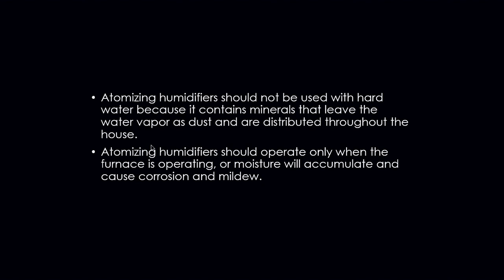Okay, atomizing humidifiers should not be used with hard water because it contains minerals that leave the water vapor as dust distributed throughout the house. Atomizing humidifiers should operate only when the furnace is operating, or moisture will accumulate and cause corrosion and mildew. So I'm going to say that again. Humidifiers should only operate when the furnace is operating, which means when our thermostat calls for heat, we are also going to send the signal to the humidifier as well. We do not want humidifiers to run all the time. They need to operate only when the thermostat is calling for heat.